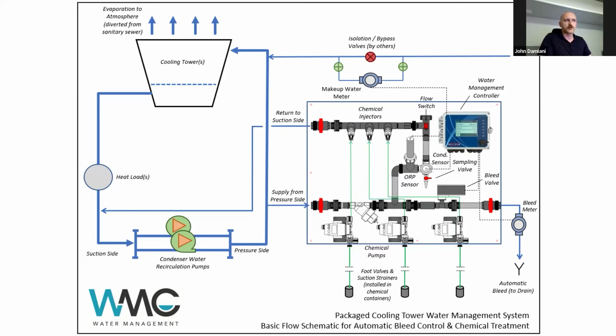Again, you can see the central controller with a makeup water meter feeding to it, so that as new water enters the system, it sends pulses back to the controller to indicate that treatment is required, which operates the pumps. And the bleed system is there, just like in the previous diagram, so as water travels through the loop, the bleed valve opens and closes as needed to send water to drain.